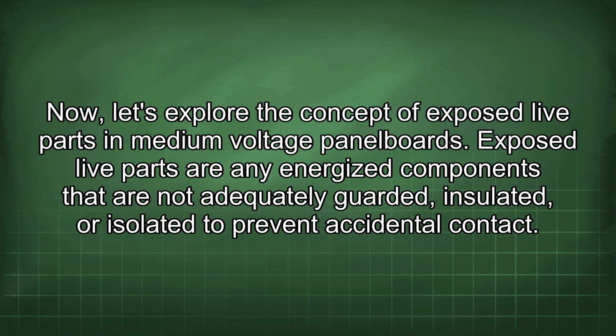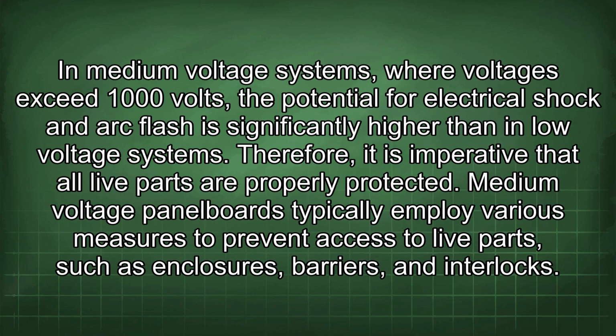Now let's explore the concept of exposed live parts in medium voltage panel boards. Exposed live parts are any energized components that are not adequately guarded, insulated, or isolated to prevent accidental contact. In medium voltage systems, where voltages exceed 1000 volts, the potential for electrical shock and arc flash is significantly higher than in low voltage systems. Therefore, it is imperative that all live parts are properly protected.